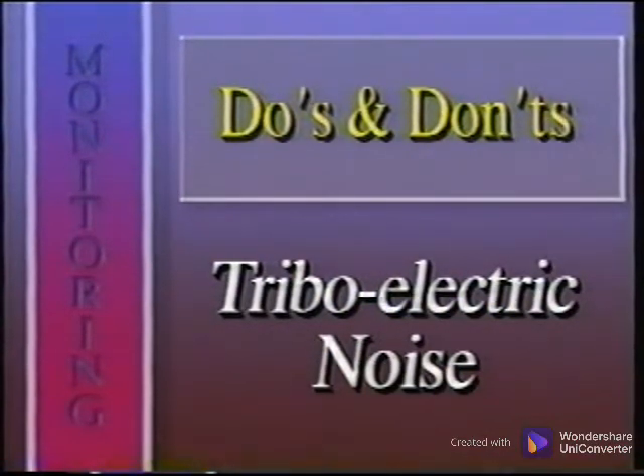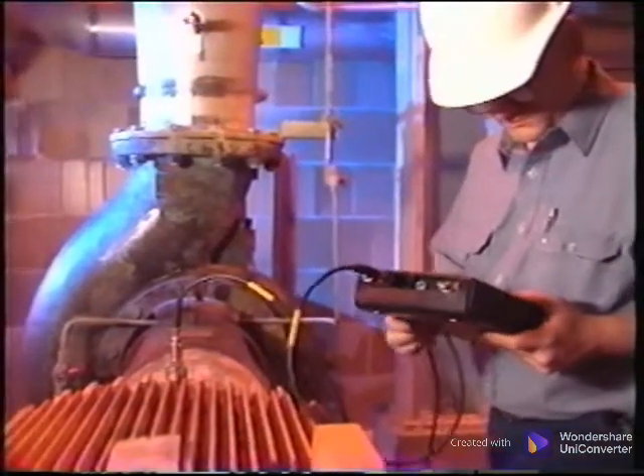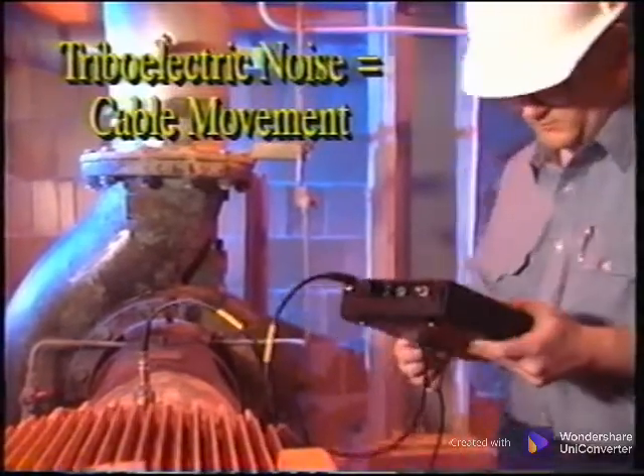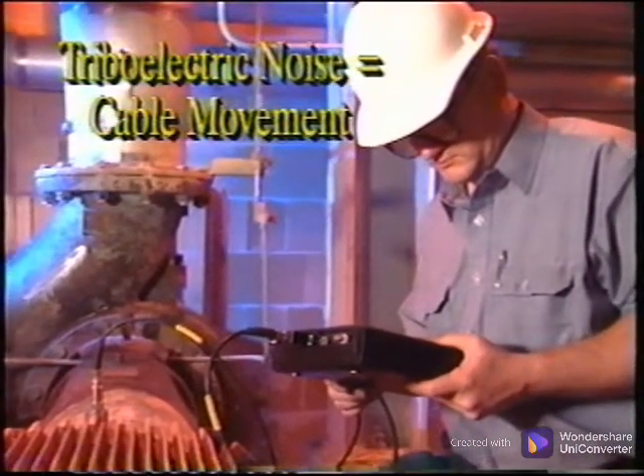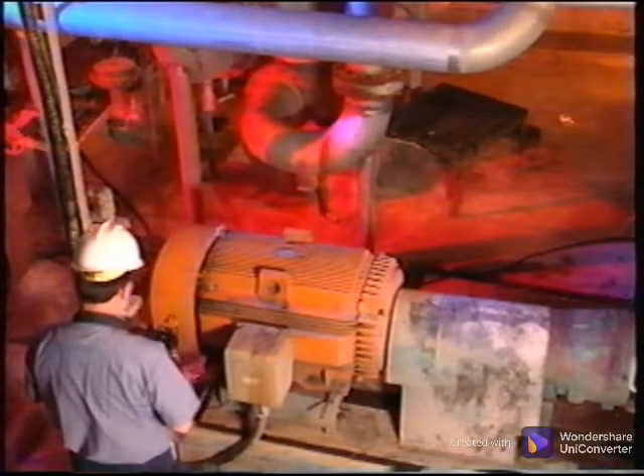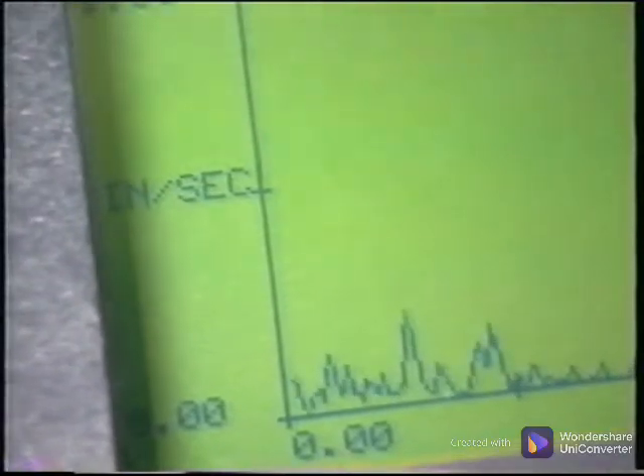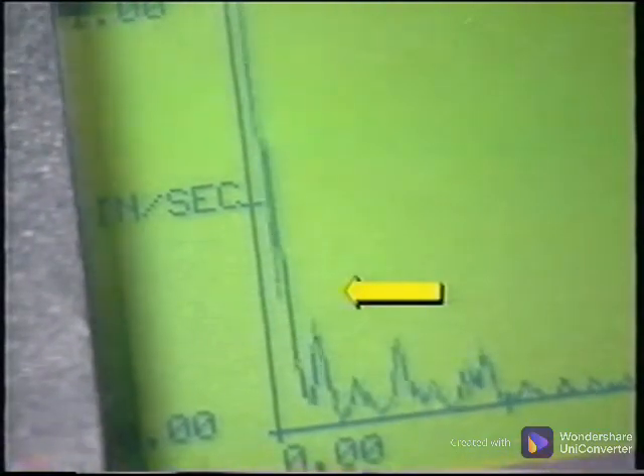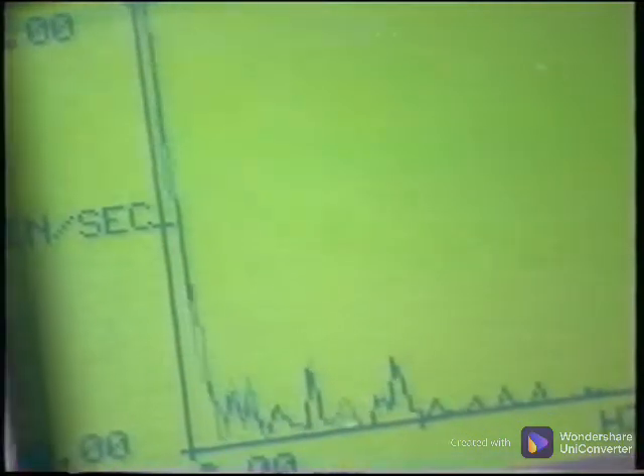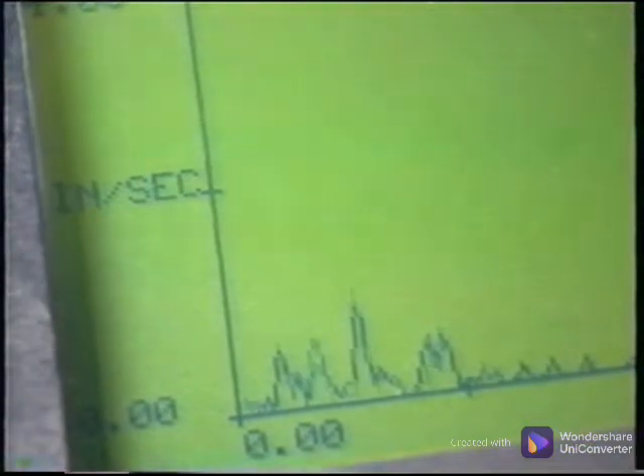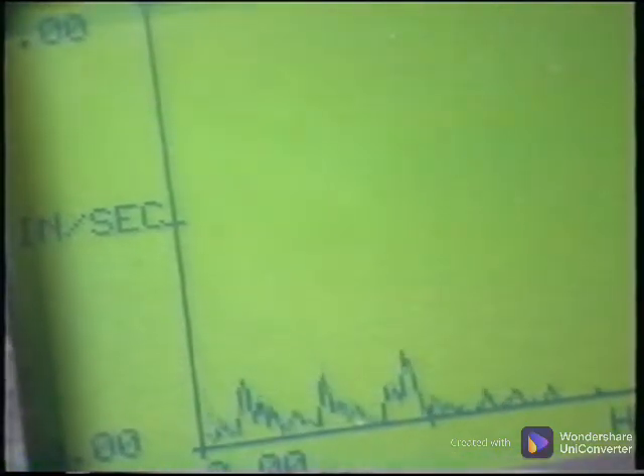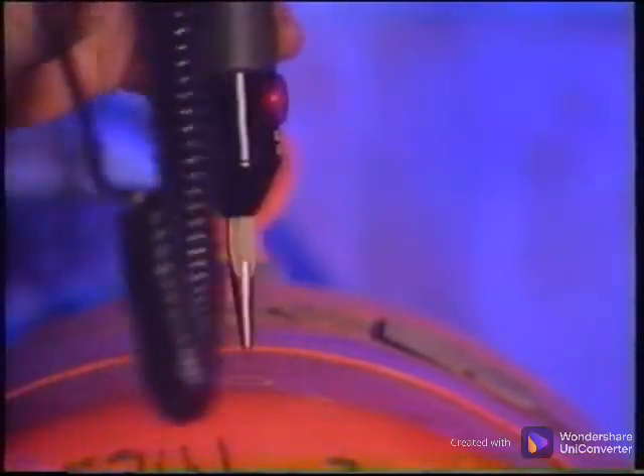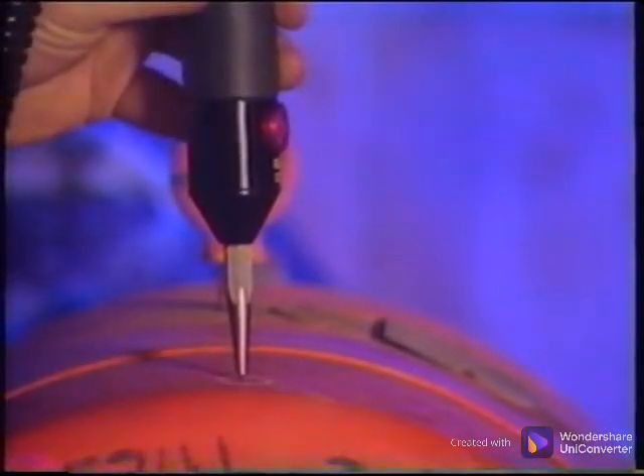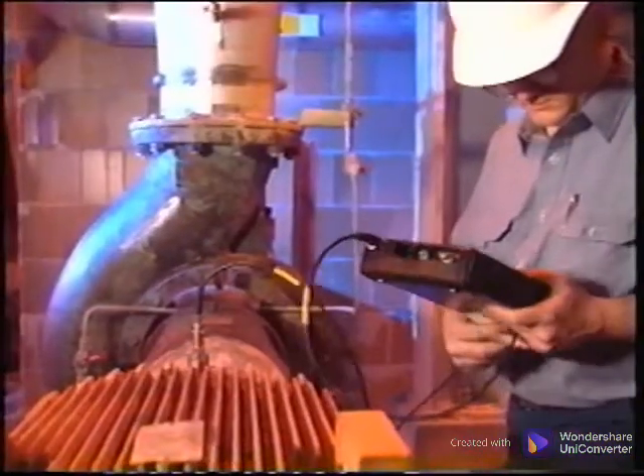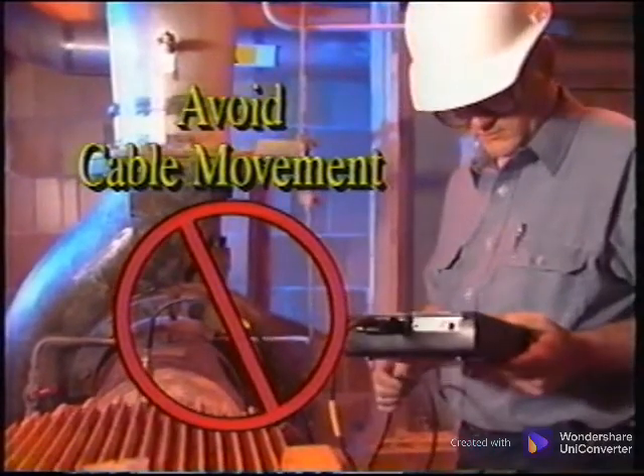Another common data corrupter is the effects of triboelectric noise. All this means is slight movements of the cable during data collection produce changes in the way signals travel through the cable, and these changes are magnified by the signal processing. Let's look at the effect of cable movement during data collection. Notice the sudden rise in energy at the low-frequency end of the spectrum. This is often referred to as a ski slope because of its shape, but is commonly due to triboelectric noise or cable movement. The ski slope is especially common when data is acquired with a stinger because of the slight continual movement of the hand and cable. During data collection, be sure to avoid cable movement, as that may add a ski slope to your data, causing unusually high readings.